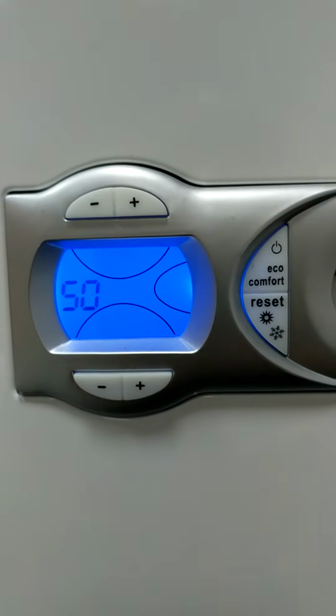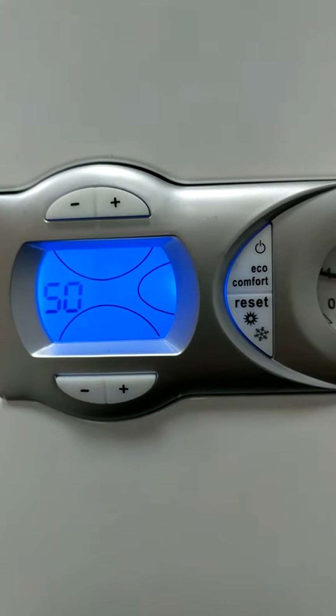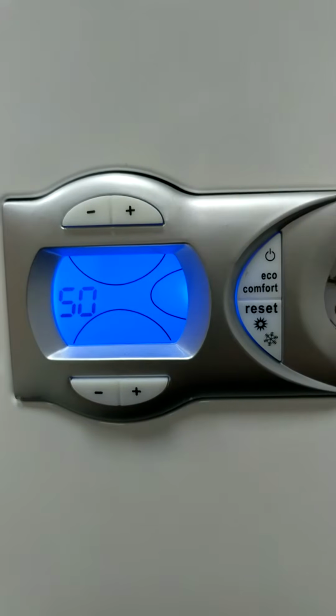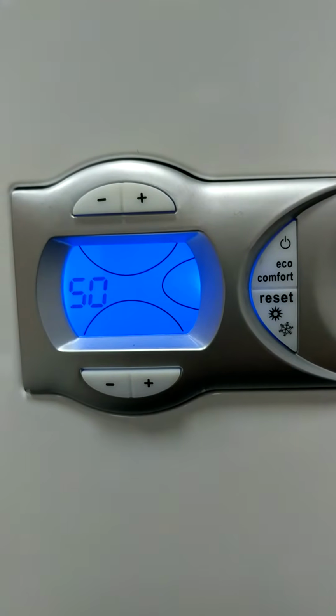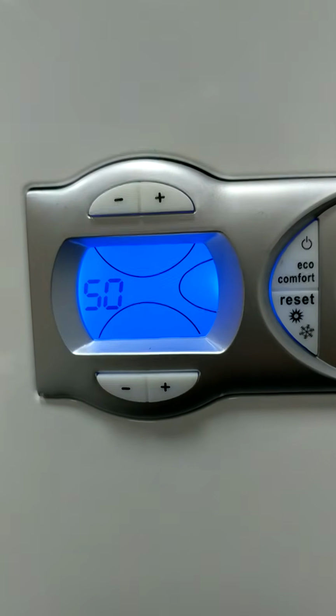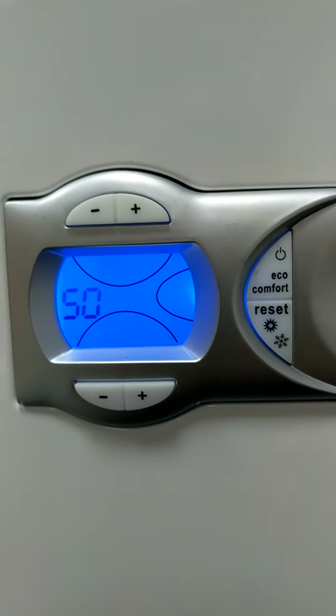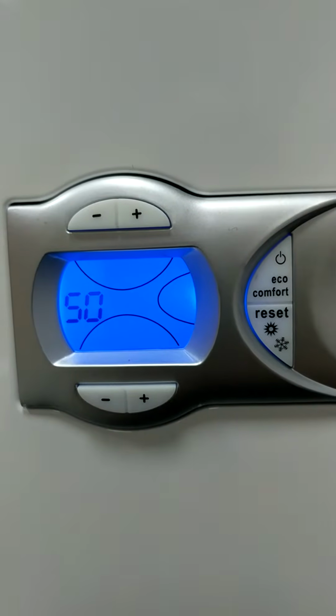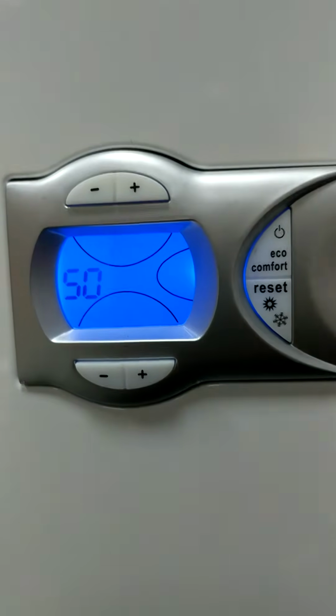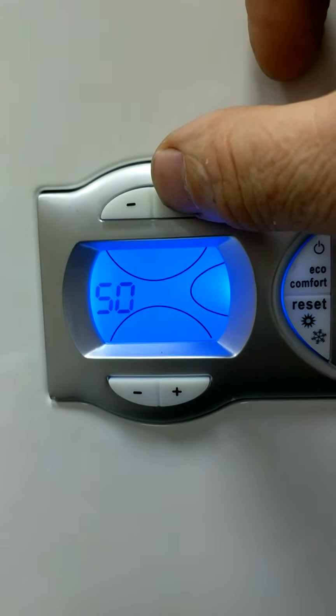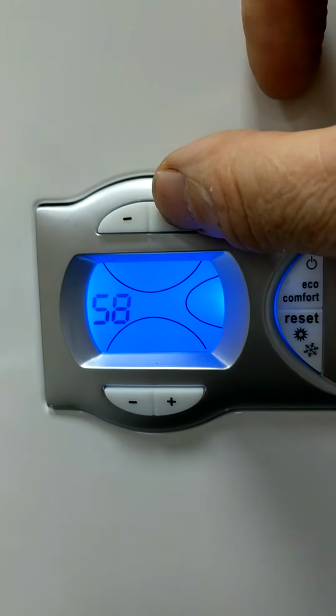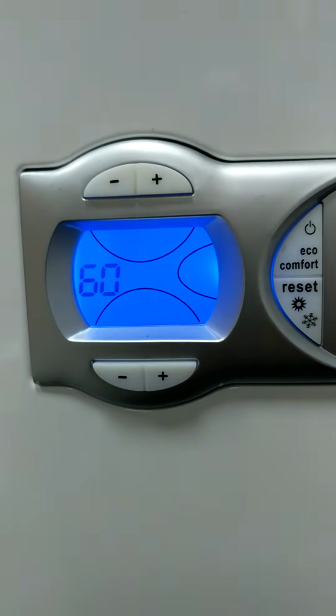So I think I said on my previous video, each radiator, as a rough guide, give it 10% of the actual output, and it's set at 100. So if you've got 4 radiators, it's 40%, 3, 30%, 2, 20%, and so on. So we're going to say we've got 6 radiators. So we set it to 60% for 6 radiators.